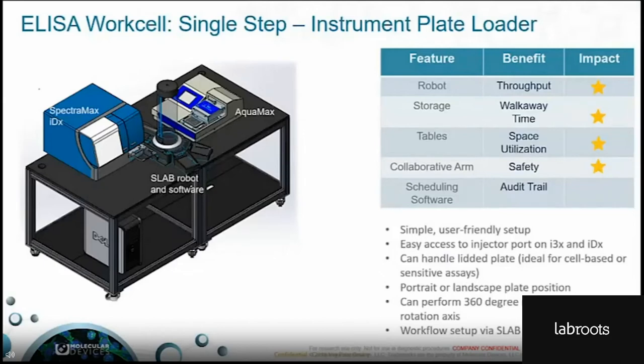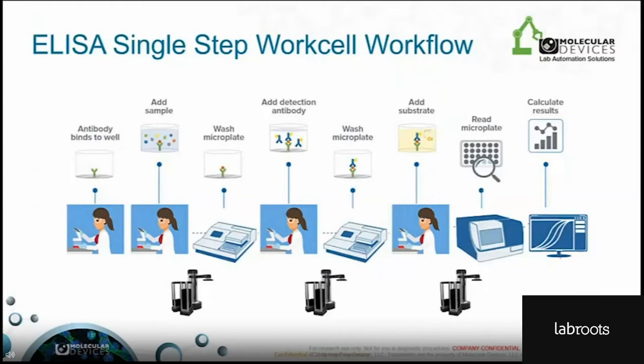The first work cell we're presenting is the single-step work cell. This employs a multi-mode microplate reader, a microplate washer, and the S-Lab robot. This configuration is defined as single-step because the S-Lab robot moves labware from its hotel storage to the AquaMax for microplate washing, and then back to the microplate reader to collect data. This setup also allows easy access to the injector port on dual-injector capable plate readers. Within the ELISA workflow, the single-step configuration still requires human intervention for adding the sample, antibody, and substrate into the microplate manually.